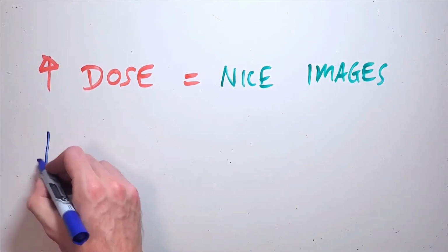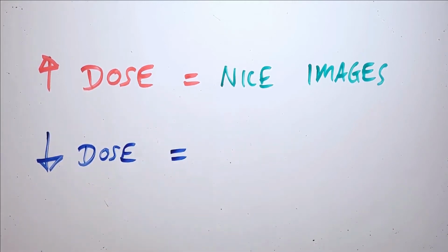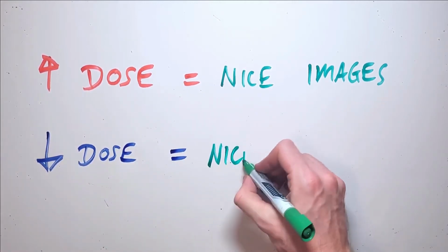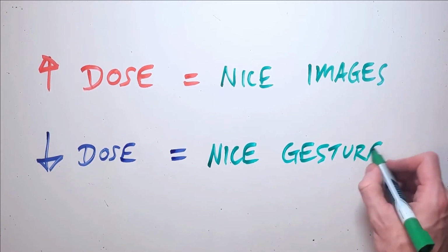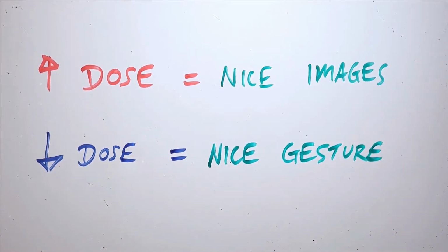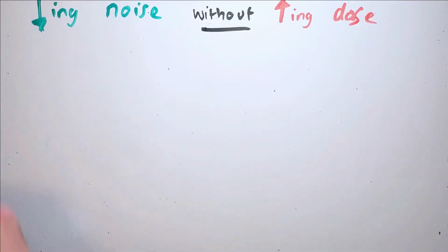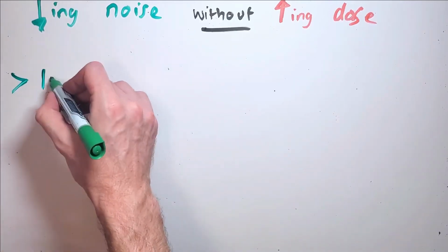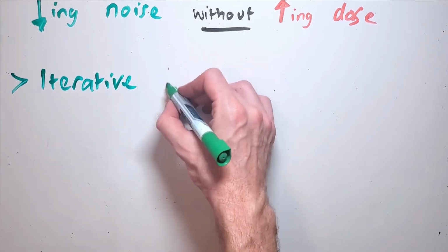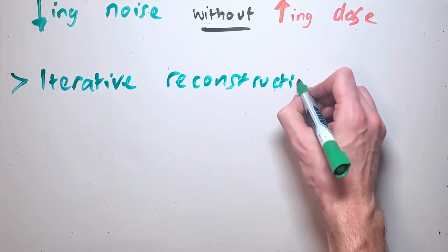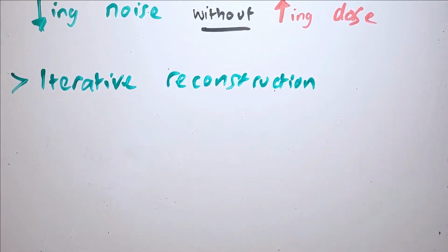What that means is that in order to decrease the radiation dose in CT, we may have to make some sacrifices in image quality. Ideally, we want to decrease noise and improve our image quality in as many ways as possible without increasing the radiation dose. Iterative reconstruction is one technique we can use to decrease our noise and improve image quality. In doing this, we can decrease our dose and settle for more noise in our original dataset, which will then be offset by these iterative reconstruction algorithms.